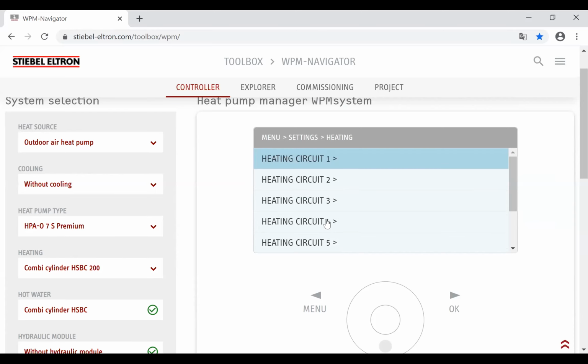All pump control, as opposed to manifold control with actuators. When we're bringing a pump off and on, particularly if we're using a mixer, with a mixer we like to run the water all the time. We like the pump to keep going. Now, people say, isn't that inefficient? It isn't. In fact, all the data we can provide can show you that the difference between running the water through the slab all the time and just changing the temperature, versus running a fixed temperature and turning it off and on, can be staggering.